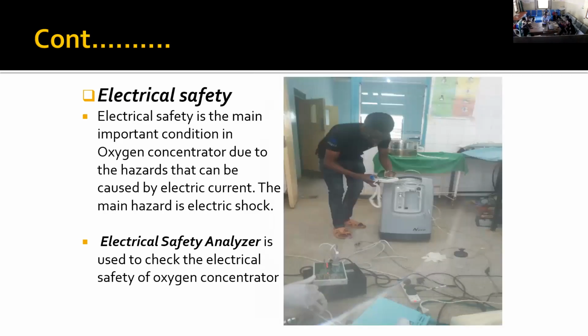Okay. So the physical inspection checklist looks like this. That is the picture of the physical inspection. To do proper preventive maintenance, you have to do the physical inspection. And that is the checklist which we have done for one of our units, an emergency unit, for one of the concentrators. You can see it clearly. It guides you on how to do the physical inspection on the machine, especially the oxygen concentrator.